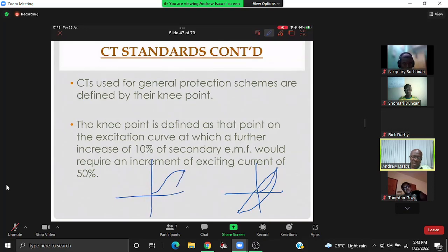So we call this cycles of magnetism. A cycle of magnetism means that you magnetize a piece of material by increasing the current in one direction. You remove the current. When you bring it to zero, you still have some residual magnetism in it, which we refer to as the remnant flux. Then, of course, you reverse the current, and the amount of current you use in reverse to remove the residual flux is known as the coercive force.